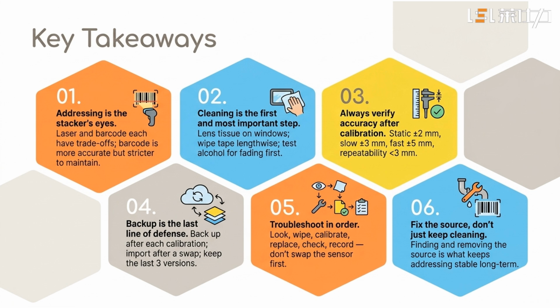Let's recap today's key points. 1. The addressing system is the stacker's eyes. Laser and barcode each have trade-offs. 2. Cleaning is the most important step, but use the right tools and methods. 3. Always verify accuracy after calibration, that closes the loop. 4. Always back up the parameters, or a sensor swap leaves you blind. 5. Troubleshoot in order: look, wipe, calibrate, replace, check, record. 6. Fixing the contamination source beats frequent cleaning. Take these standards back and check your own equipment against them.